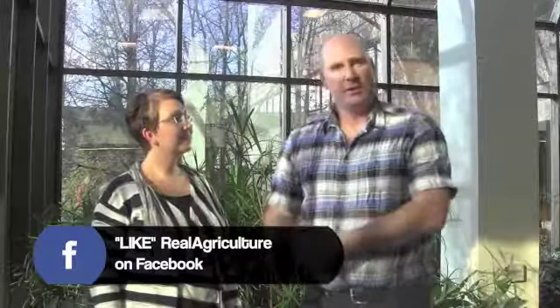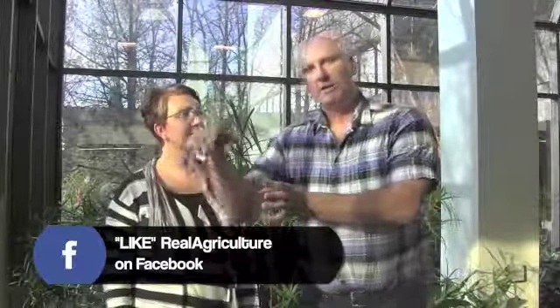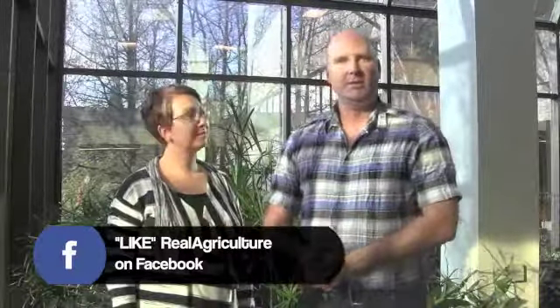So now your pre-treated water, as we call it, that's been stored will go through another filtering process, and you can take it as far as you want, right down to making bottled water with it. So our technology is a pre-treatment, which just helps everything down the line work a lot better. Okay, so you pre-treat, and then you disinfect, which is always needed, and then afterwards you can put on reverse osmosis, whatever you want for that purified water. Yeah, it's always a treatment train. Not one piece of equipment is going to do everything. With any surface waters, you start with aeration, then pre-treatment, which is our system, and then you filter it further, disinfect, and take whatever further steps you want. So it's not going to replace the whole process, but it is a step in the process, yes.